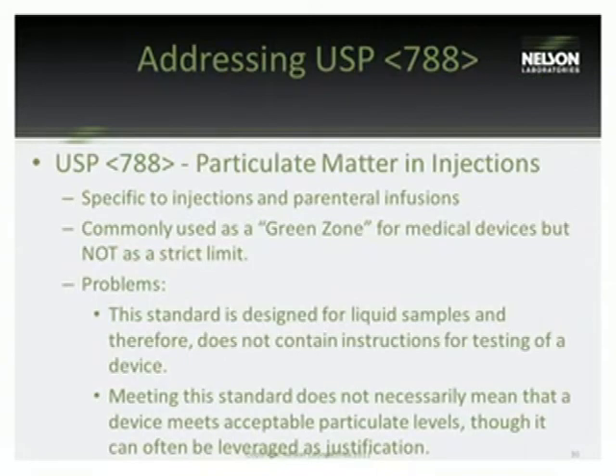Now, addressing the USP 788, we frequently get questions from many of our clients as to whether or not they can adopt the 788 to their device. Much of this has come from historical use of the 788, and some of it has come from just the fact that the 788 is the most common standard used in particulate matter testing. But some things to keep in mind is that the 788 was written specific to injectables and parenteral infusions, just liquids. Sometimes it is commonly used as a green zone. Even here in the lab at Nelson, we typically will regard a device to be rather clean if it's below the 788 specifications, but it's not really designed for medical devices.